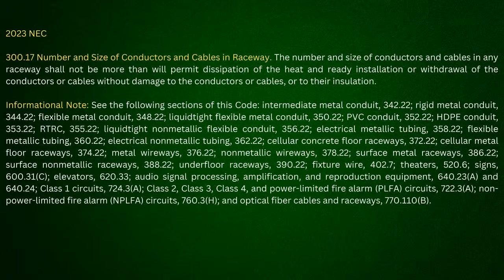I don't know how anybody can argue this up to this point, but let's go a step further. If I look at 300.17, it gets into the number and size of conductors and cables in raceways, and it says the number and size of conductors and cables in any raceway shall not be more than will permit the dissipation of heat and ready installation or withdrawal of the conductor. So, once again, I've been stating it's a sleeve. You got it open end at the other end. That allows for what? Dissipation of your heat.